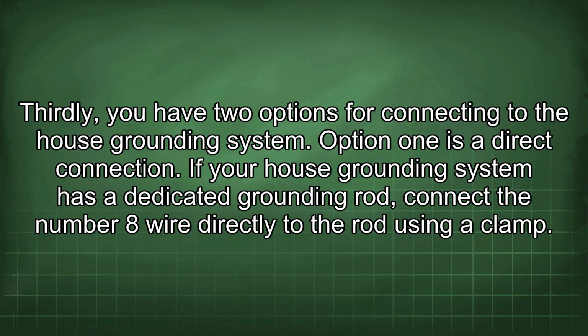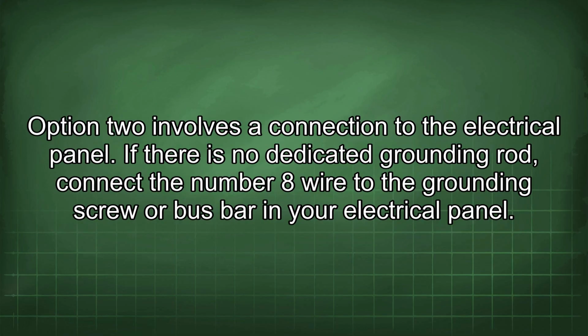Thirdly, you have two options for connecting to the house grounding system. Option 1 is a direct connection. If your house grounding system has a dedicated grounding rod, connect the number 8 wire directly to the rod using a clamp. Option 2 involves a connection to the electrical panel. If there is no dedicated grounding rod, connect the number 8 wire to the grounding screw or bus bar in your electrical panel.